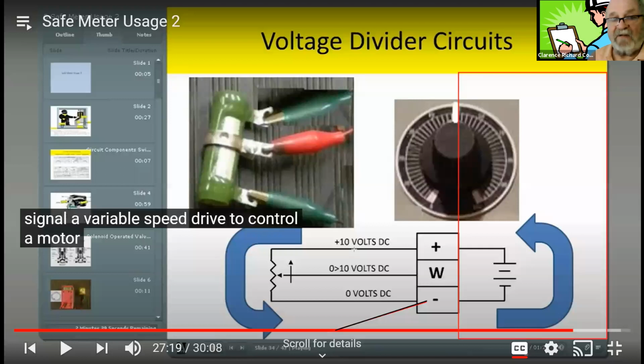Well, a VFD is going to have a couple of inputs. One input is going to see the run command. Are you giving a run command? Are you giving a contact close? You flip that toggle switch and say start. So if you did do that, then you've got to start looking: am I giving it a speed signal? So we're going to be doing a check on a speed signal. So we set our meter for 10 volts DC or 20 volts DC.